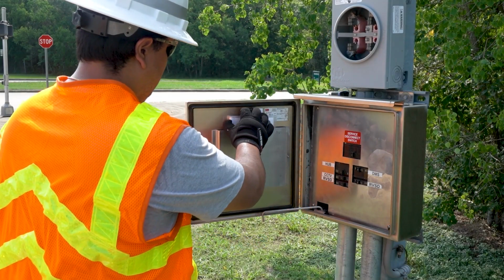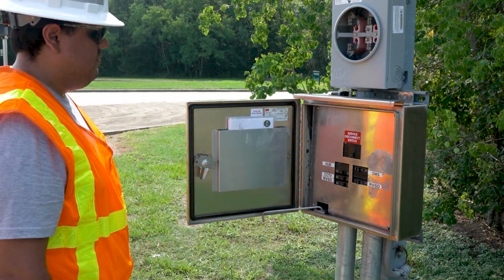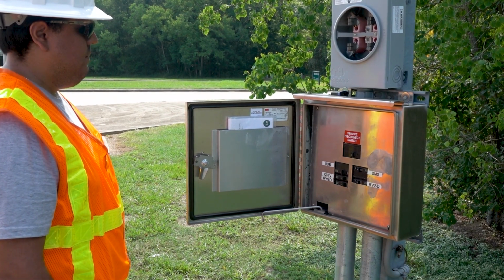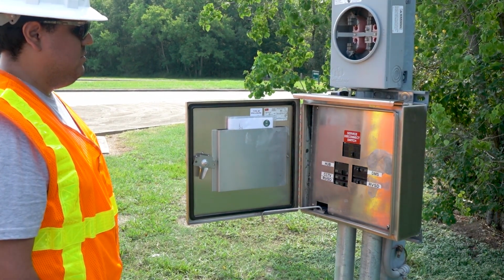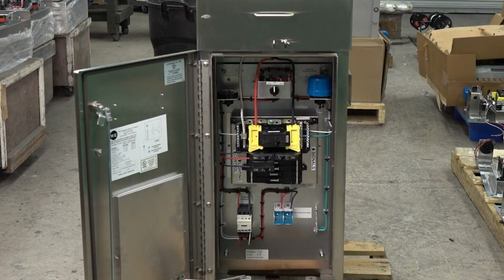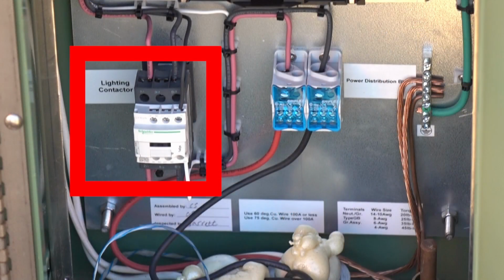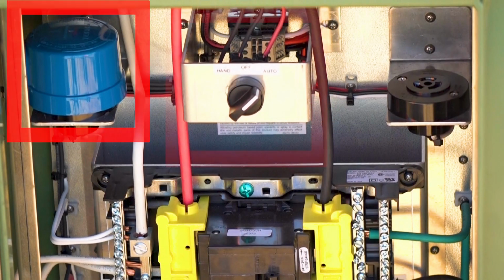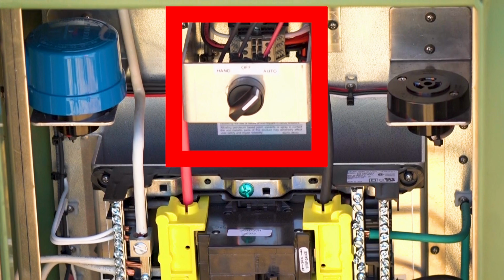This training video will aid TxDOT personnel inspecting the installation of a Type D electrical service. The enclosure is custom-built by a UL 508 industrial control panel shop. This type of service is not to be confused with an off-the-shelf type of service. The off-the-shelf type will not have an internal lighting contactor, enclosure-mounted photocell, or a handoff auto 3-position selector switch.